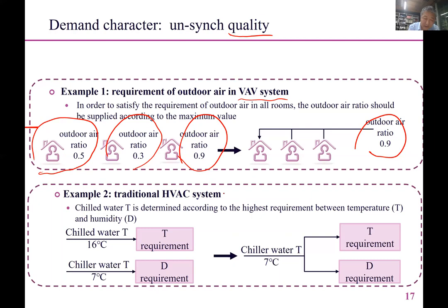Here is another, the chilled water. We use that not only for temperature control, but also for humidity control. But normally, for sensible heat, as soon as the water temperature comes to 16 degrees C, it's good enough. However, if you do the dehumidification, you need 7 degrees C chilled water.